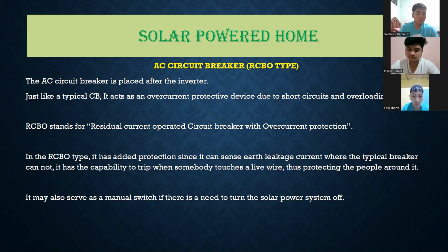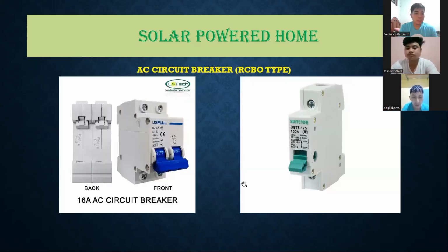Now, in a properly wired house, we have 3 wires, right? A live, a neutral, and a ground. If the AC circuit breaker, RCBO type, detects a minimum current of maybe 4 milliamps, depending on the RCBO, between live and earth, then it trips, thus protecting whoever or whatever connects the circuit between those 2 lines. Here we have the RCBO, a dual gang. It looks much like a normal circuit breaker.